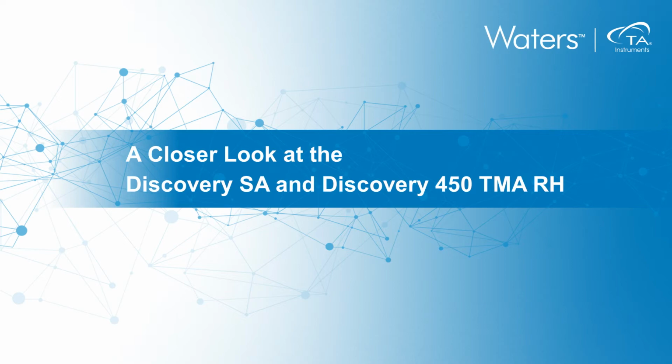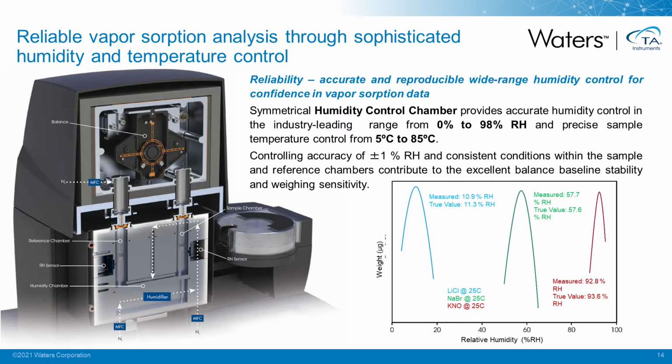So let's take a little bit of a closer look now at these two instruments. So this is a cutaway view of the Discovery SA. You can see the balance at the very top there. This is a symmetric design. So the sample side and the reference side are exposed to the same temperature and relative humidity conditions.